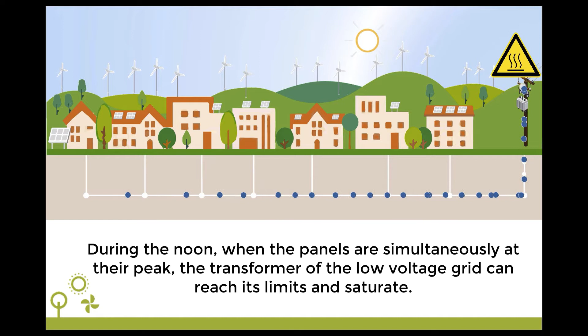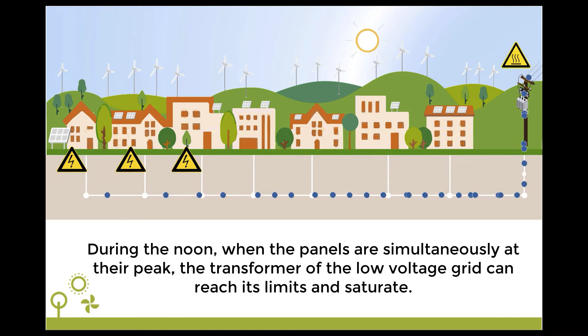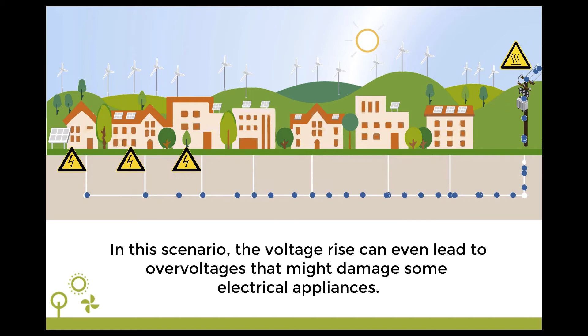During the noon, when the panels are simultaneously at their peak, the transformer of the low voltage grid can reach its limits and saturate. In this scenario, the voltage rise can even lead to overvoltage that might damage some electrical appliances. Now the sun is setting, but during the day a lot of electricity has been sent to the distribution grid.